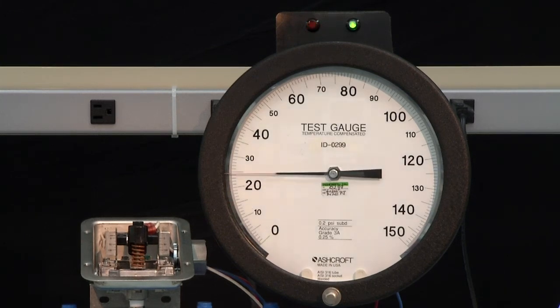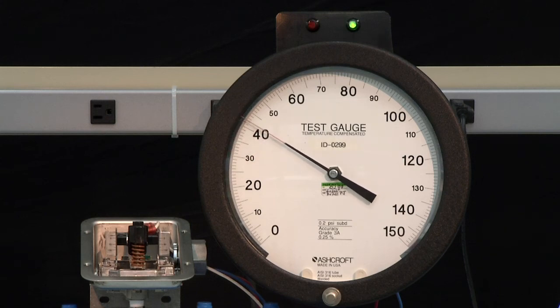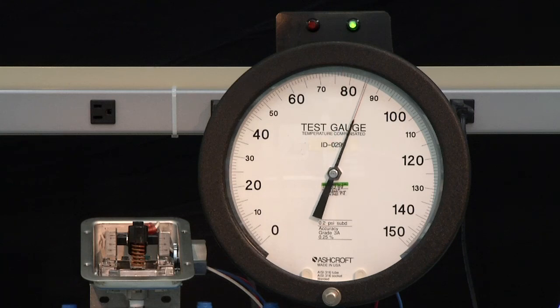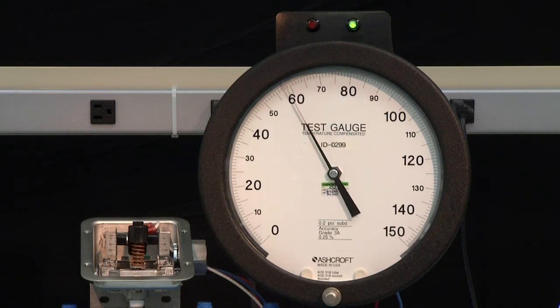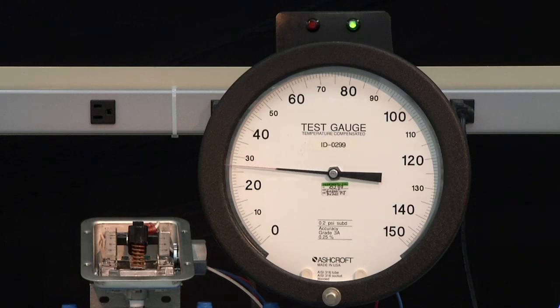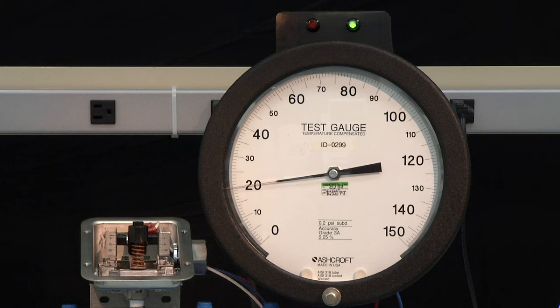So we will rise up to 100 and then we will lower the switch down to just before our desired set point quickly. And from there we will go slowly until the switch resets which is our decreasing set point. And this is very close to 20 on the decrease.